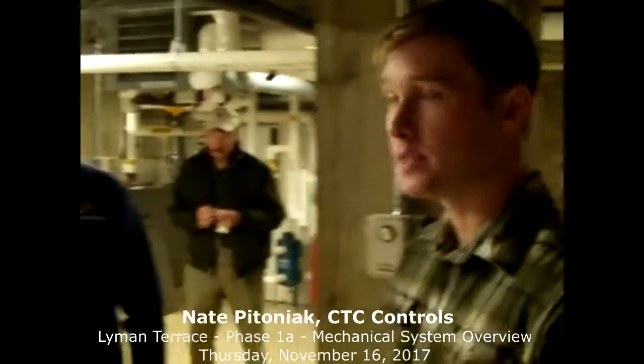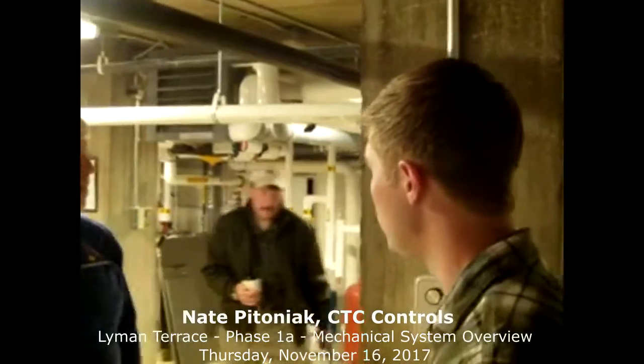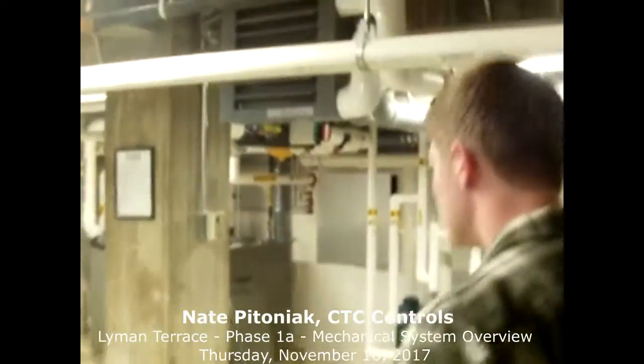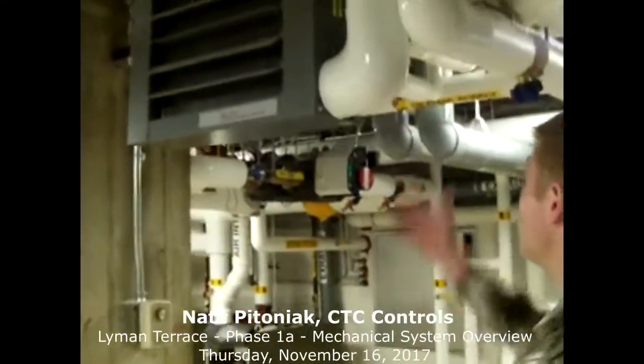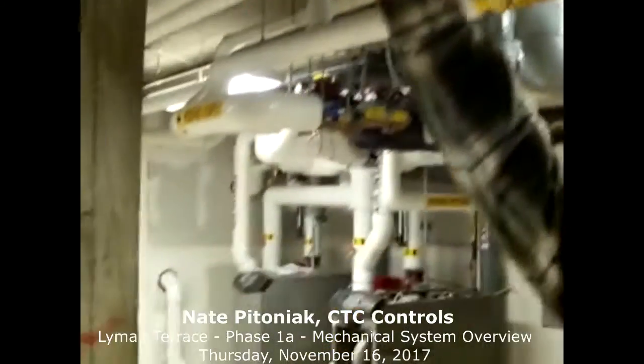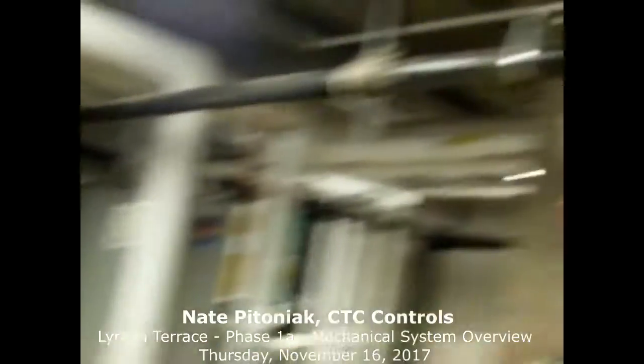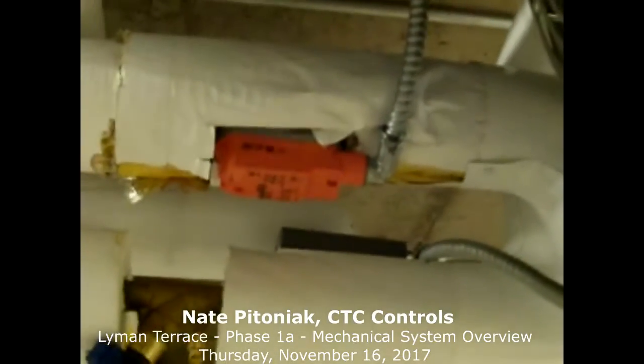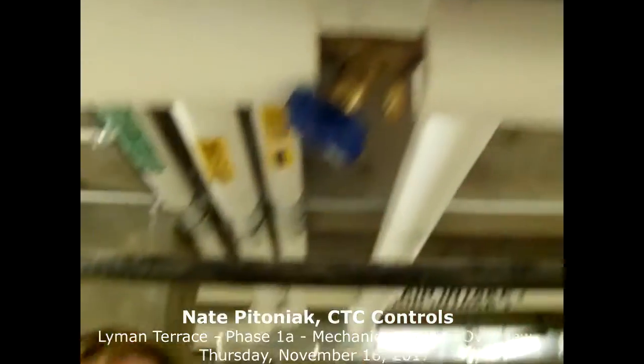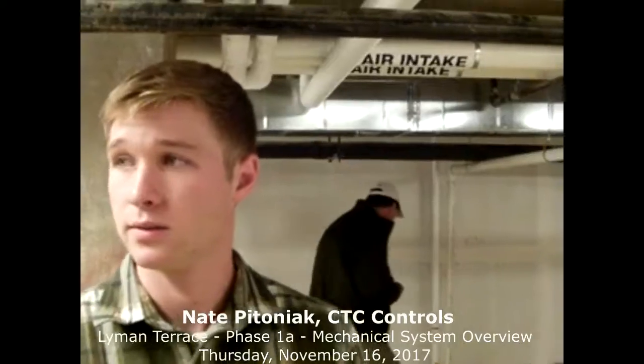Okay. And the last piece of equipment down here is your unit heater that has its own thermostat as well. Whenever this calls for heat, you have a zone type valve here. This is the same model you have in all of your apartments. The way it operates on a call for heat, your valve is going to open once your aquastat sees that coil's hot, it's set for 110 right now. Then it turns your fan on. It's just a way to prevent the unit from blowing cold air.